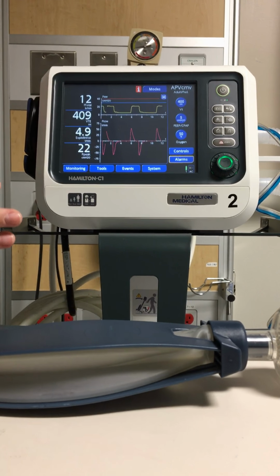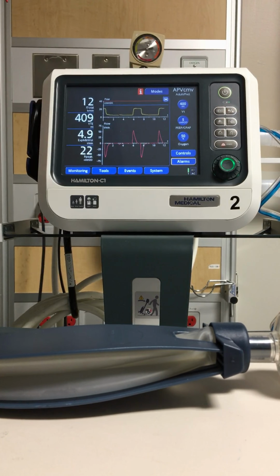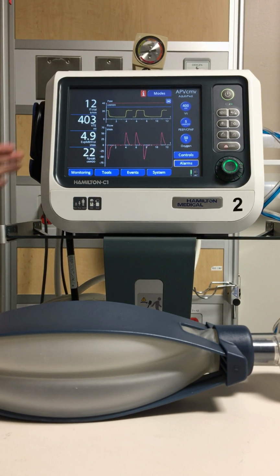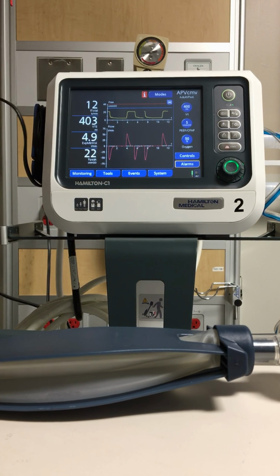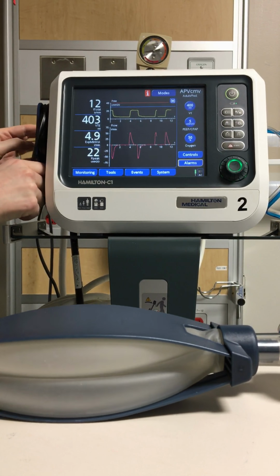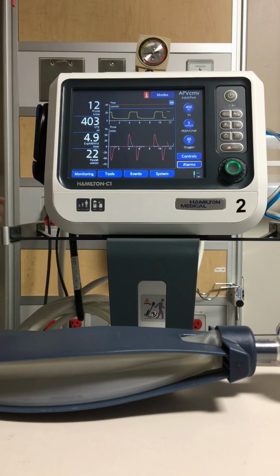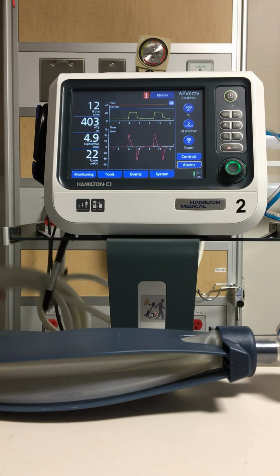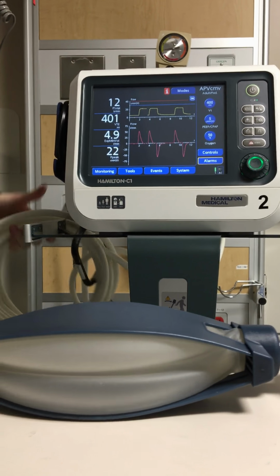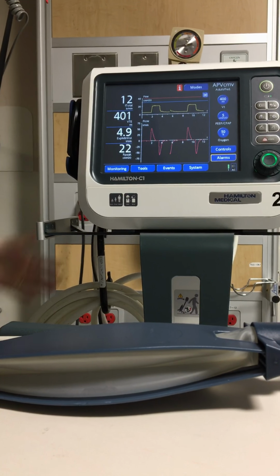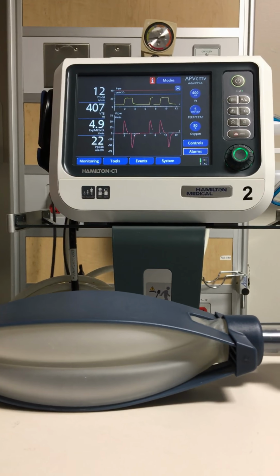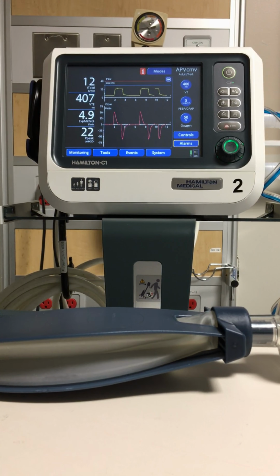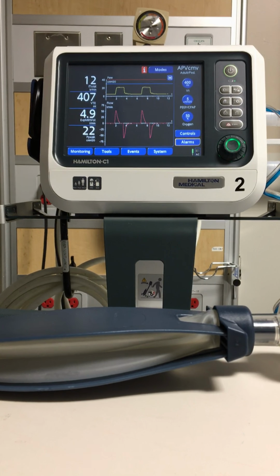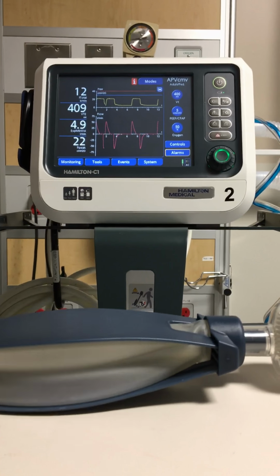In terms of the setup of this ventilator, you can see the graphics, which I will go over eventually here. It has an AC power cord that attaches to the wall, but also has a battery, which is why it's a ventilator that we use for transport. It has high pressure oxygen tubing that we can attach to the wall or to the oxygen tank that is located on the cart for the ventilator itself. So again, it makes it very good for transport.